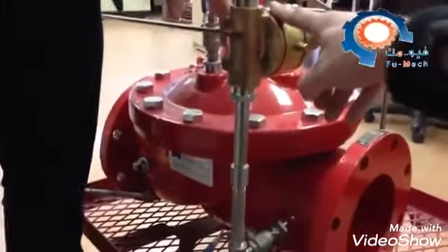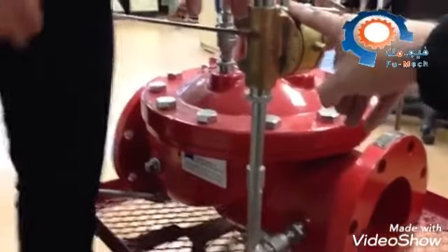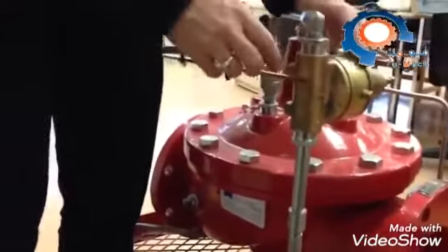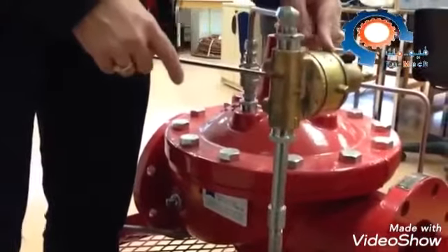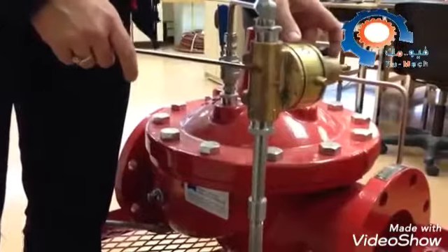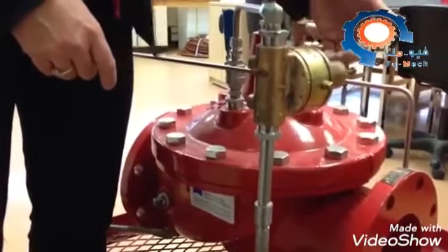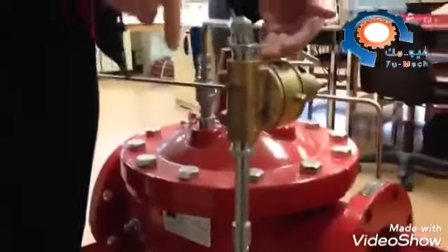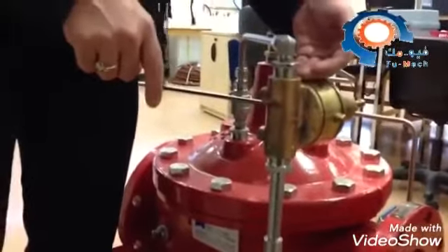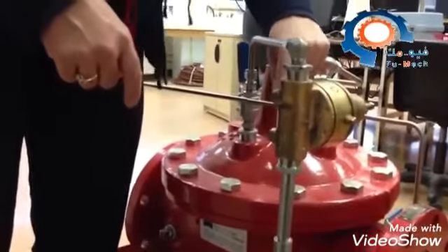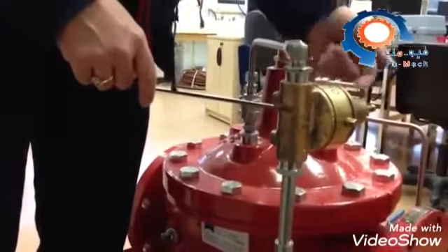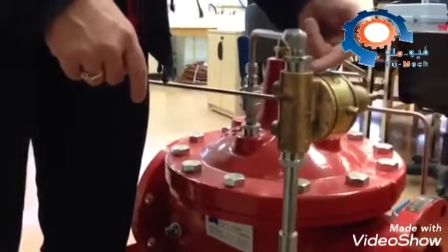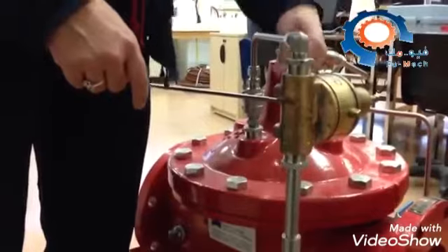Because this starts putting water onto that diaphragm. Like right now, when the pressure is below 80 psi, the spring force is winning on this. So it's forcing the stem to be down, which brings the disc in contact with the seat. So unless there's enough pressure in the sensing chamber, the spring will always be forcing this valve closed, because it's a normally seated valve.